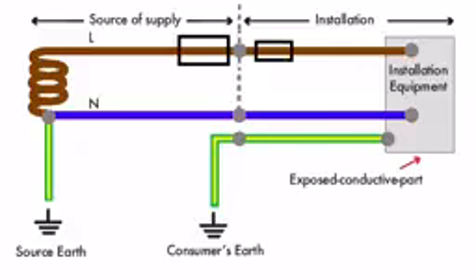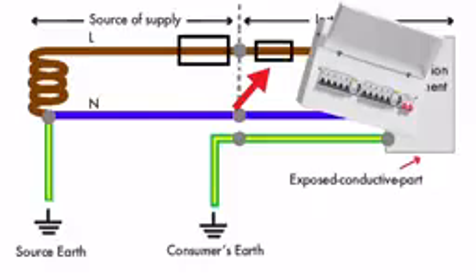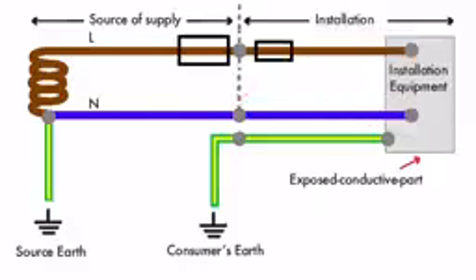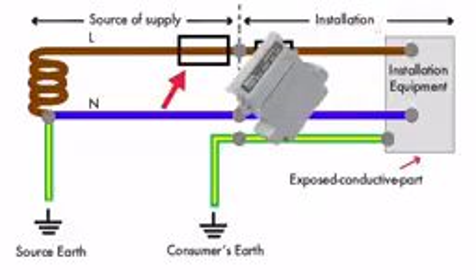However, as always, overcurrents and short circuits will be dealt with by the fuse housed within the consumer's unit for each individual circuit. The installation wiring will still be the same as previously stated in TNS and TNCS earthing arrangements, with a separate line, neutral and circuit protective conductor. Also, the metering equipment will be the same, as well as the supply authority's cutout fuse being either 100, 80 or 60 amps.